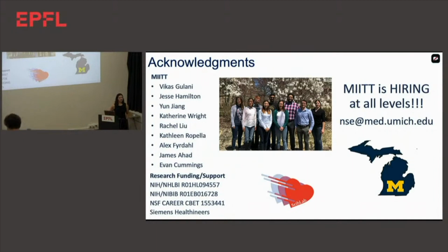On one of your first slides in the upper left corner, you were showing this tiny, teeny sequence, right? And then later, when you showed the correlation between the different T1 values and T2 values, it seemed to me all of a sudden there is a dynamic range issue. Because in your sequence, you use an inversion pre-pulse in order to increase the dynamic range, I think, of the T1.